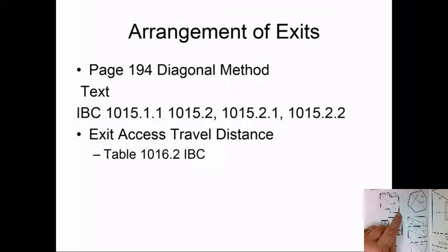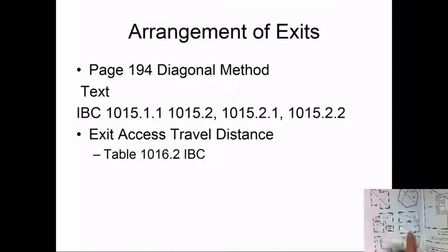If it's 50 feet, half of that is 25 feet. So if I have one doorway here, I've got to go a minimum of 25 feet. If I have 2 rooms, because these are intervening rooms, remember you have to walk through one room to get through. That means I'm measuring this total length, and half of it is what I've got to do. These 2 doorways have got to be at least half apart, and then these 2 doors have to be at least half the distance. Whatever this total is, half of it. Okay? So you look at that and understand.